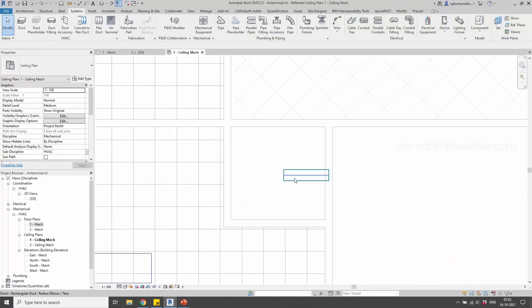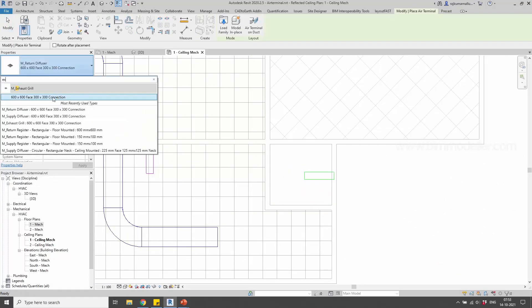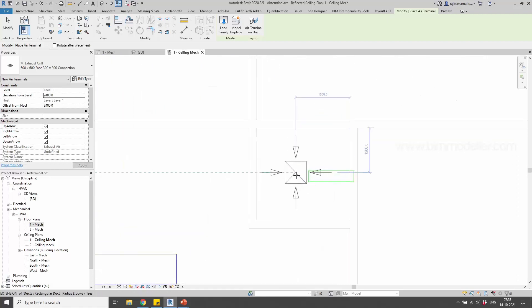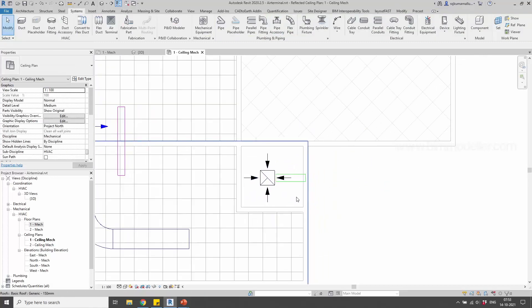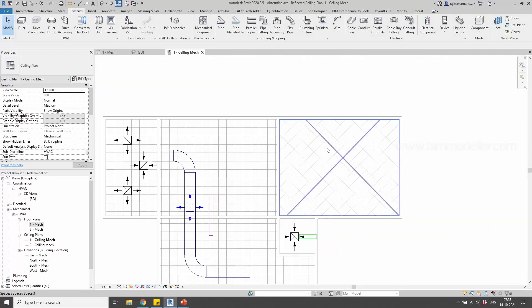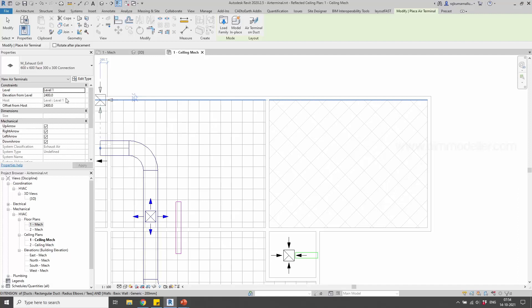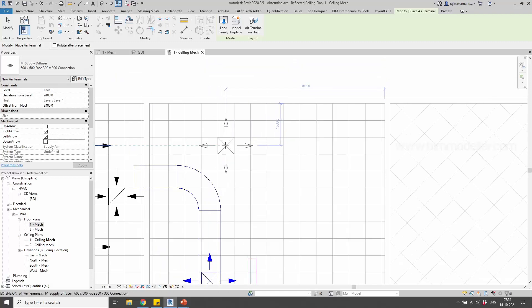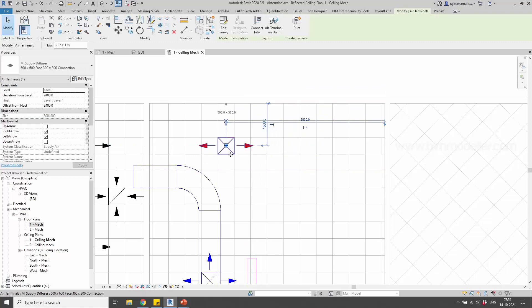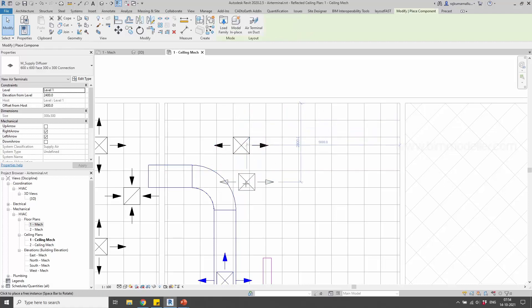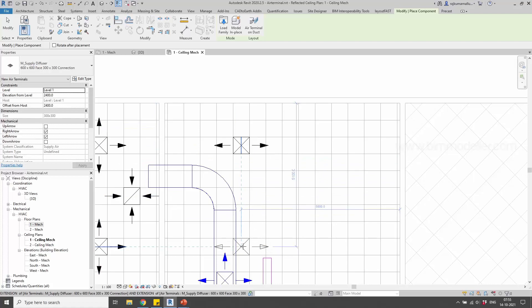Going to the next option — there is an exhaust grill. You can go ahead, select the exhaust grill, and place it in this room using height 2400. The ceiling is not placed in this floor yet, but not a problem, we can place it here. We also need to place supply grills in a different direction. In the instance properties, other than height, we have up arrow, right arrow options — you can turn on up and left arrows, so the diffuser applies air in two directions only. Create similar with the same arrow settings and place it wherever needed.